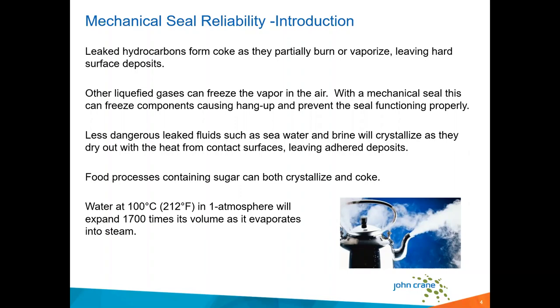If we consider those dangerous fluids, and then look at less dangerous or less volatile fluids, they may still experience a change in phase, but it's not likely to be as severe. But in terms of the scope of reliability, nobody wants an unreliable seal, so state change is still something to be mindful of. Even in a condition of, say, seawater or brine, you're still going to have crystallization and drying out from the heat at the contacting surface. So you'll still have adhered deposits that you need to contend with to help prolong the life of the seal.